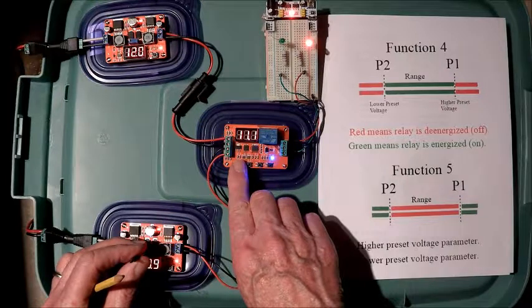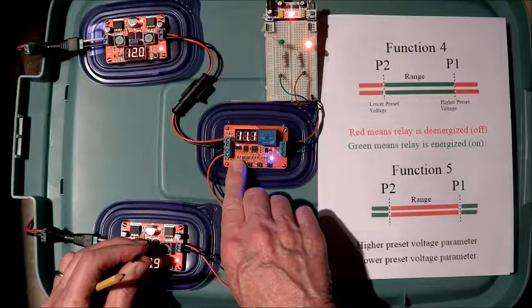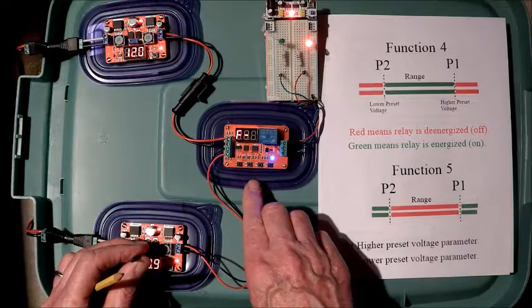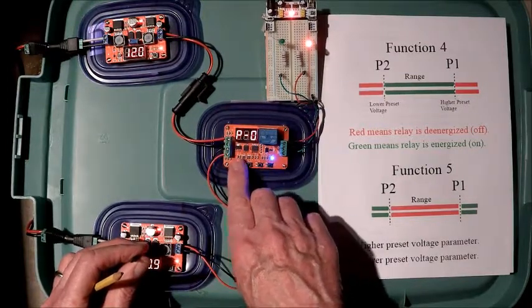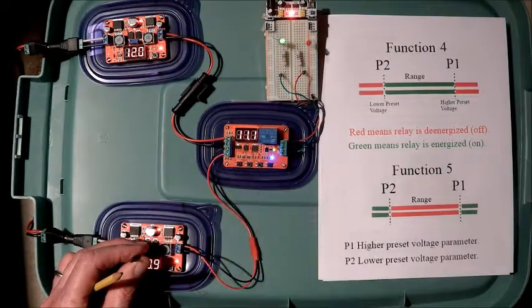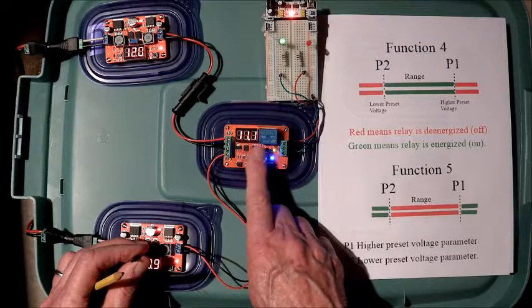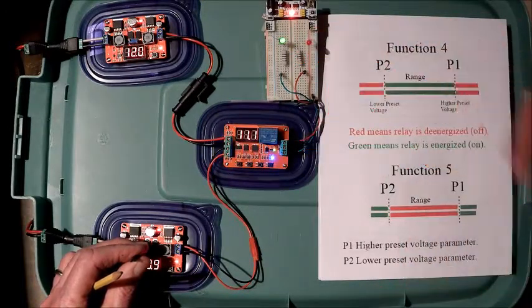Function 5 is just the mirror of that. Coming out of Operational Mode. Going to Function Select. Coming down to Function 5. Setting it in. Going to Operational Mode. We are above the high preset value, so the relay is on, as indicated by my green light. Within the range, the relay will be off. Just the opposite of what Function 4 did.